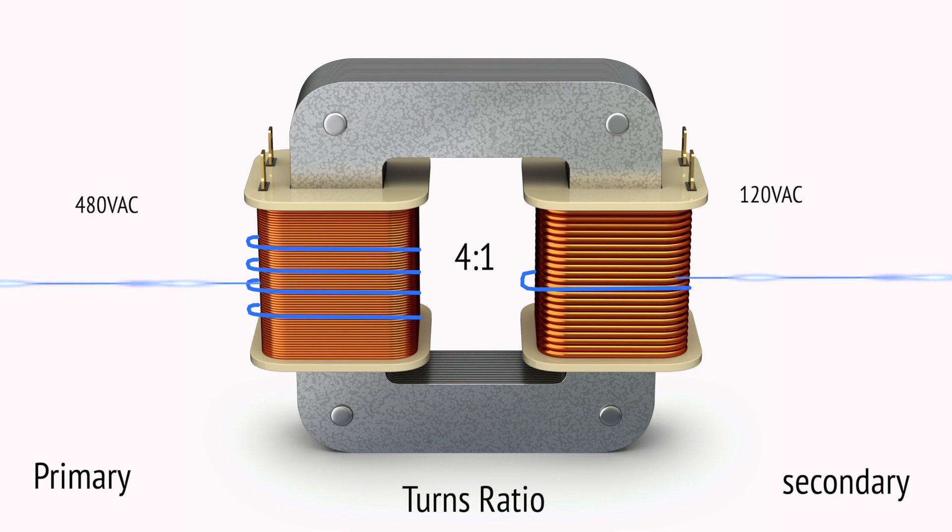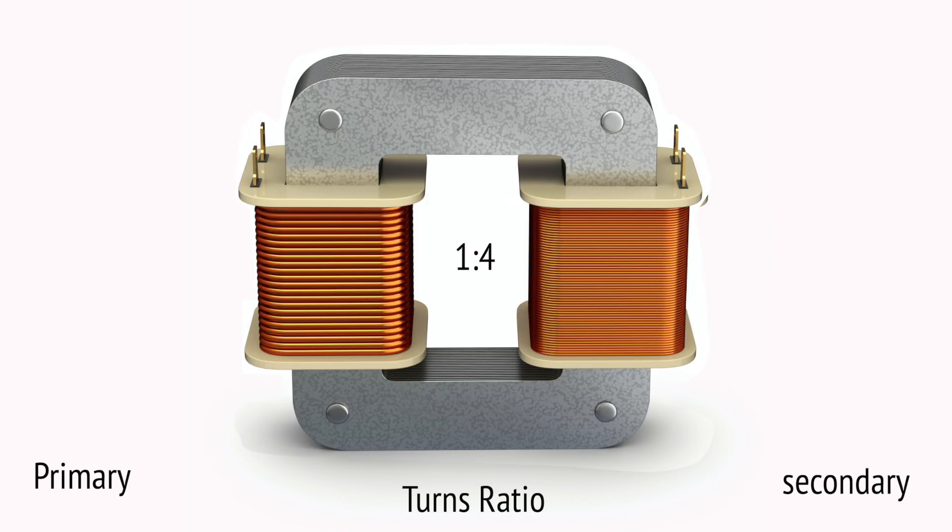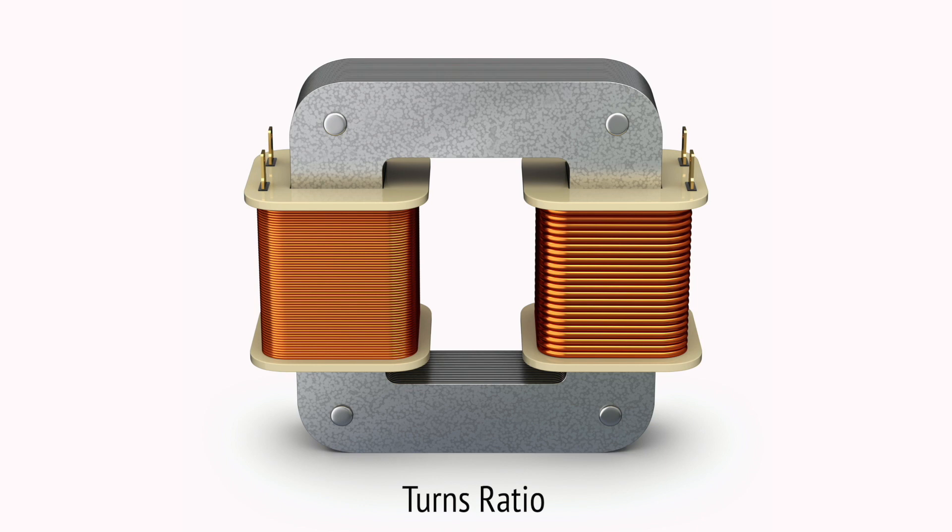The exact opposite is true for a transformer with a 1 to 4 turns ratio. This transformer would have 1 turn on the primary for every 4 turns in the secondary. Inputting 120 volts AC to the primary winding will produce 480 volts AC at the secondary winding. The actual number of turns is not important, only the turns ratio.